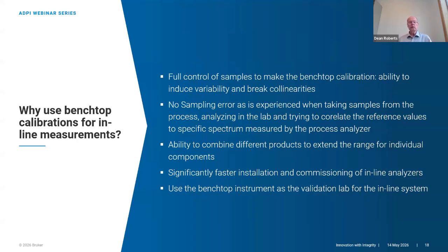Another big criteria is that there's no sampling error. So sampling error is when you are taking a sample out of the process, doing the reference chemistry on that sample, and then trying to equate those results back to the spectrum that was measured by the analyzer. The sampling error is the time difference between when you actually pulled that sample and the spectrum that you measured. And if you have a very consistent process, then that's usually not a very big deal because the process doesn't change too much, but it can happen. And if you have sampling error where it just doesn't match the calibration, you have to be able to go back and justify why that sample is different in terms of its prediction. So you can take it out of the calibration and be able to continue developing it.